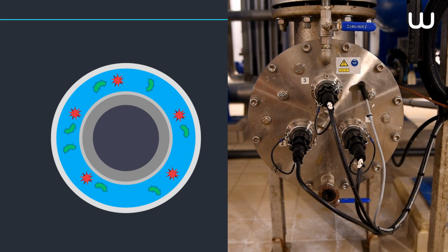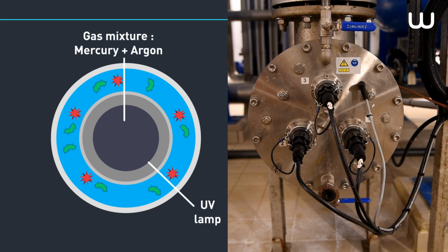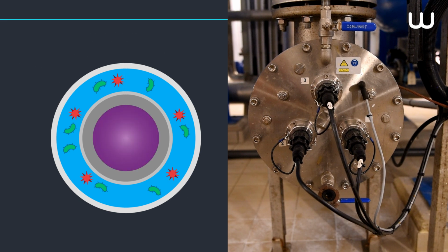Now, UV light is produced by mercury and argon vapor lamps. Now, each lamp is placed in a quartz duct transparent to UV light, which protects them from coming into contact with water. Now, an electrical shock is applied between two electrodes in the lamp, thereby exciting mercury atoms which emit ultraviolet light. Water flows in fine layers in the middle of the quartz ducts.